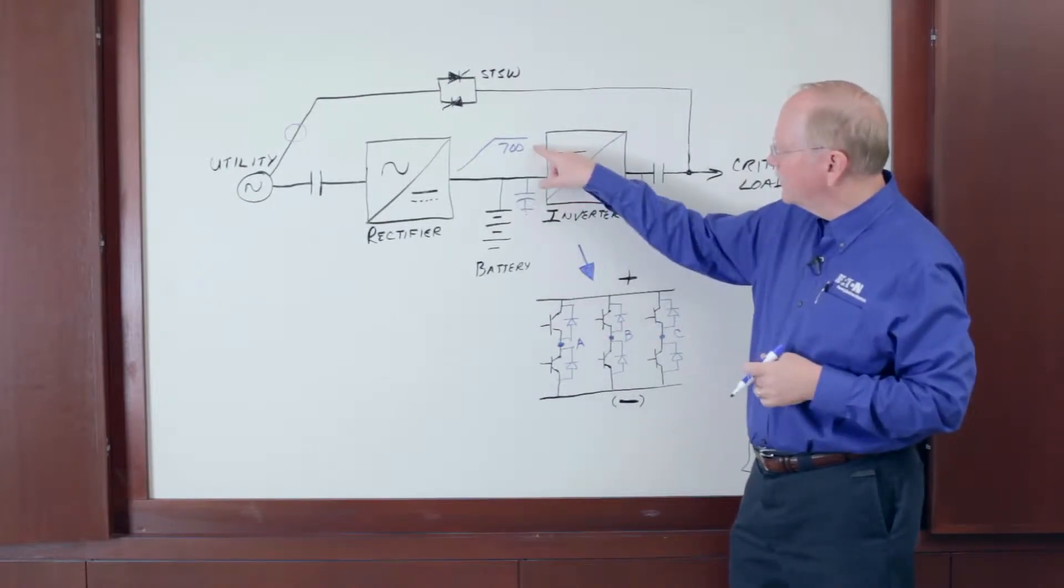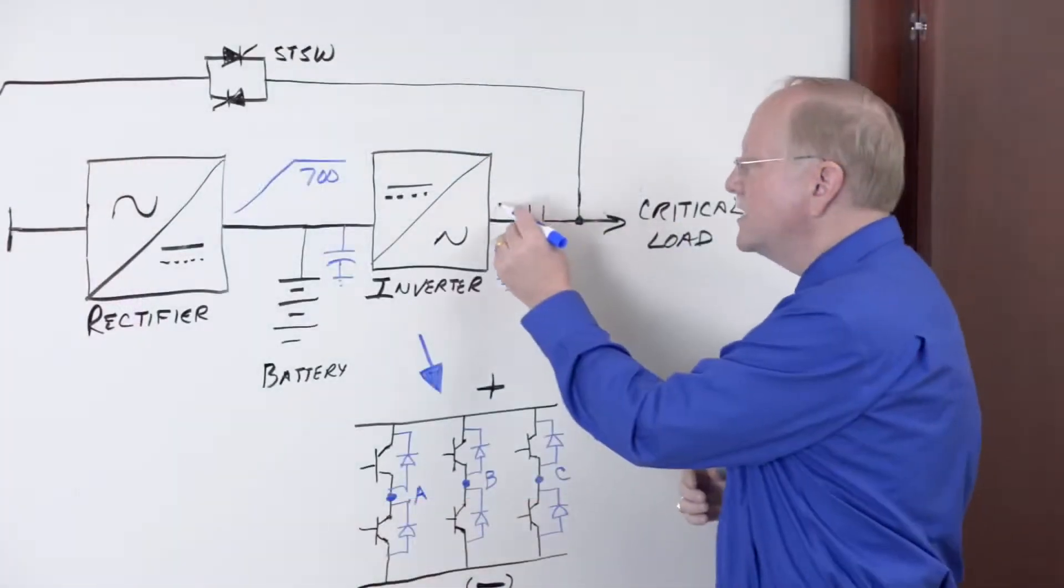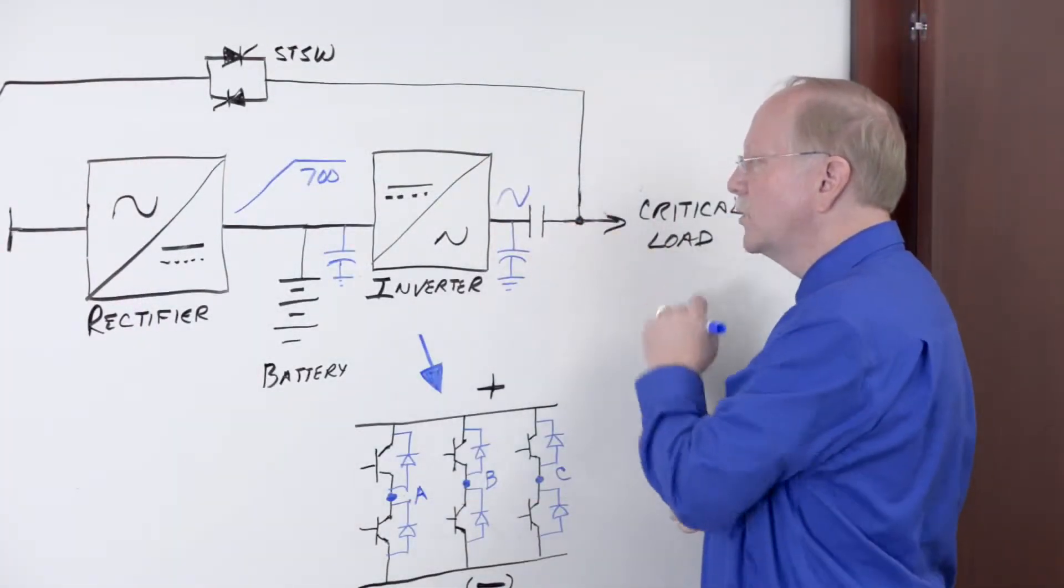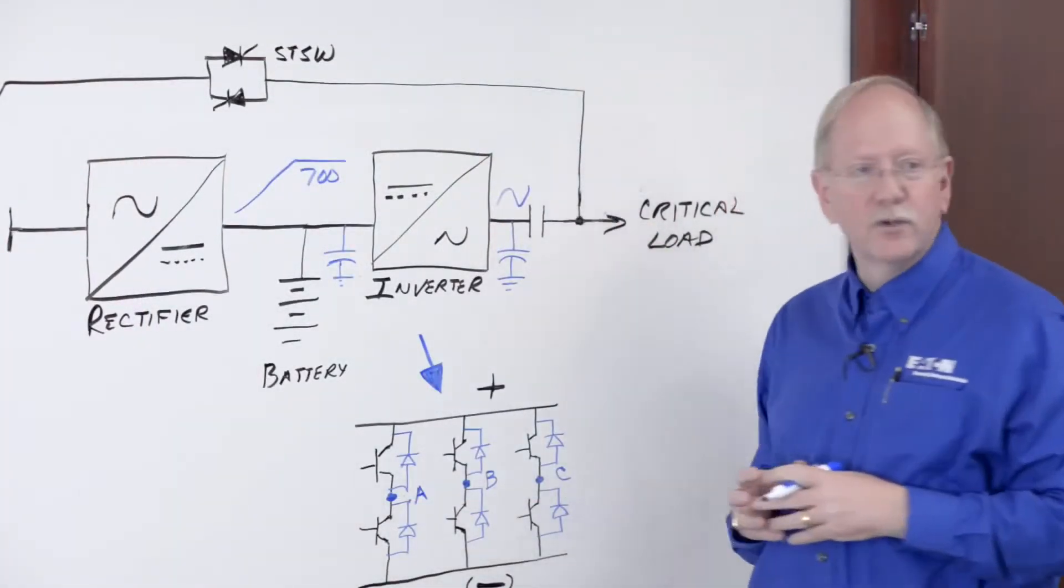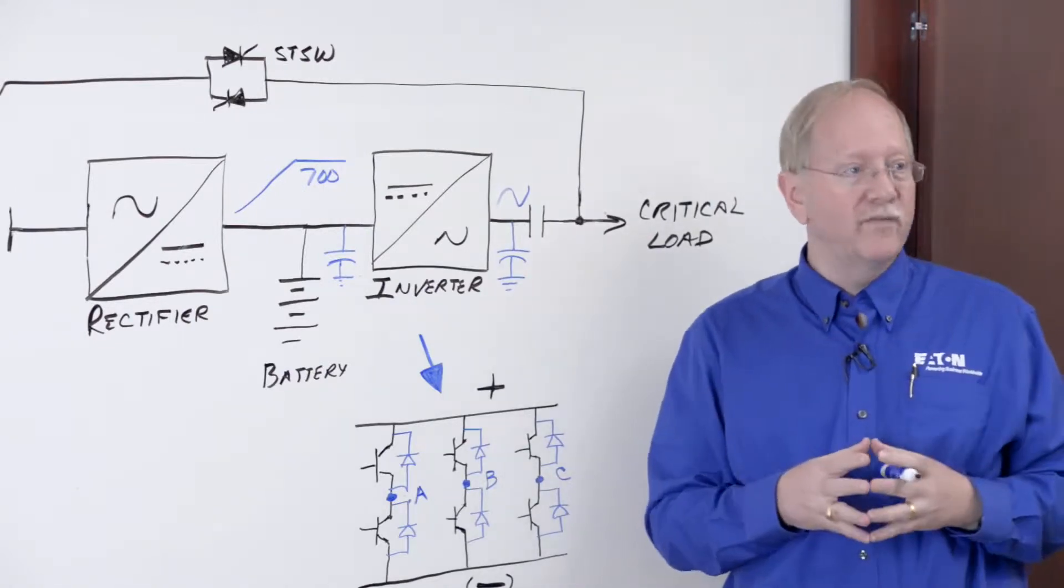Then once the 700 volts appears, the inverter can start, take DC, make AC, but this AC output of the inverter has to be in sync with the critical bus before we can close the output contactor. That's another delay of 10 to 15 seconds to wait for sync.